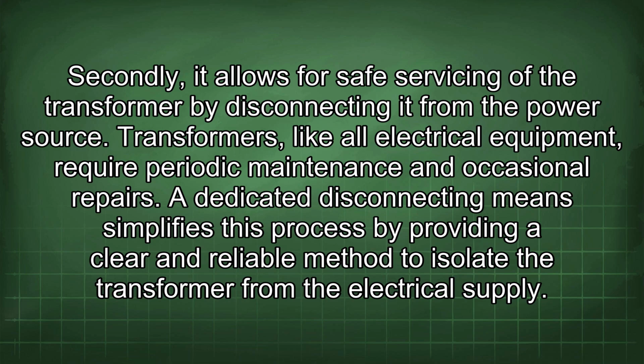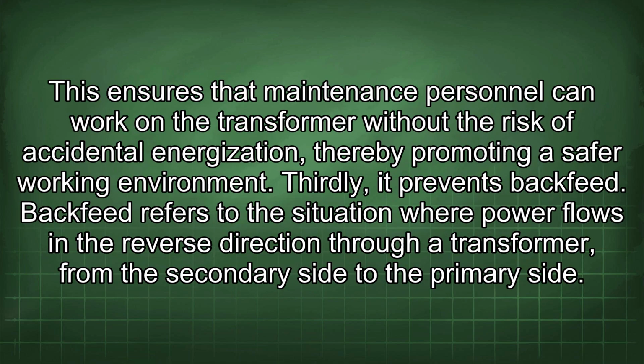Transformers, like all electrical equipment, require periodic maintenance and occasional repairs. A dedicated disconnecting means simplifies this process by providing a clear and reliable method to isolate the transformer from the electrical supply. This ensures that maintenance personnel can work on the transformer without the risk of accidental energization, thereby promoting a safer working environment. Thirdly, it prevents backfeed.